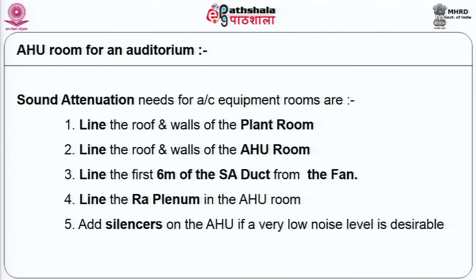I have on this slide five parameters which are listed. These are done for normal air conditioning because the equipment that you get on the day you install it is good, and it might meet your requirements. Even with the best of bearings, the best of greasing, and the best of maintenance, over a period of time the noise tends to increase, and as it increases very gradually, people who are in charge of maintenance tend to overlook it.